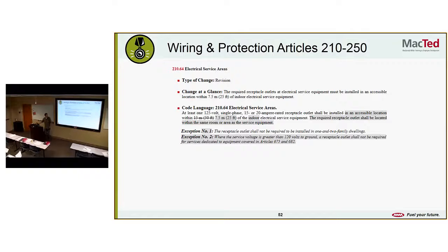So it looks like the receptacle outlet will not be required to be installed in 1 and 2 family dwellings. So in a single family residence or a 2-family, you don't need that next to the panel. Because it's talking about next to the electrical service panel. So in a house, you don't need that. And they've added exception 2, where the service voltage is greater than 120 volts to ground, a receptacle outlet shall not be required for services dedicated to equipment covered in Articles 675 and 682. So you can go to those articles and find the exceptions. But in your house, it's not required.